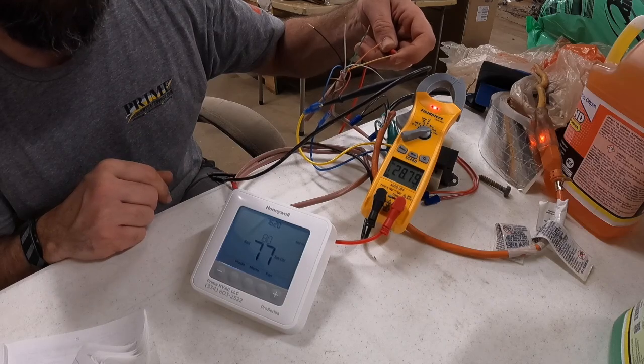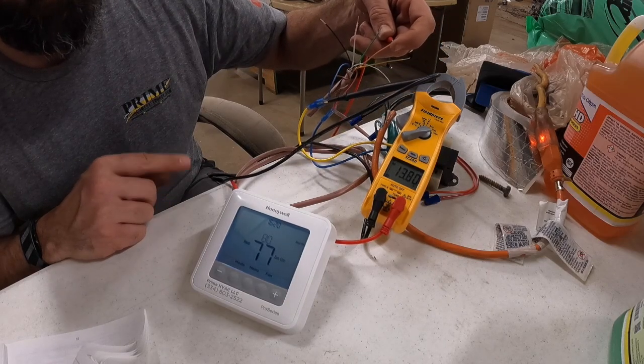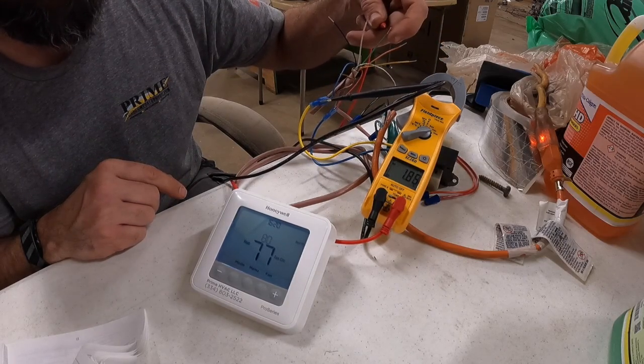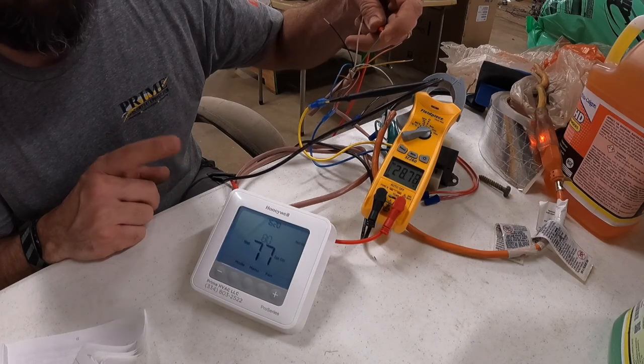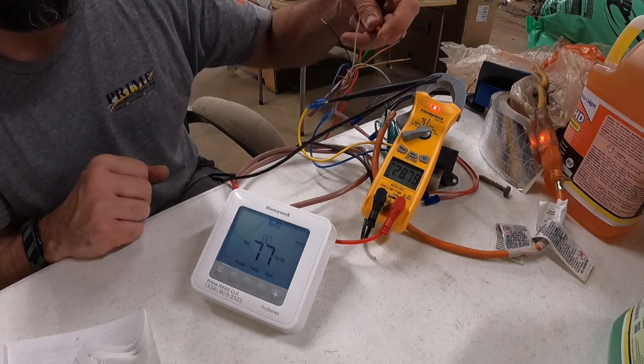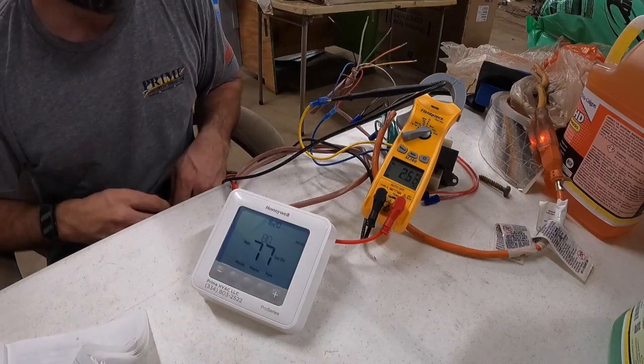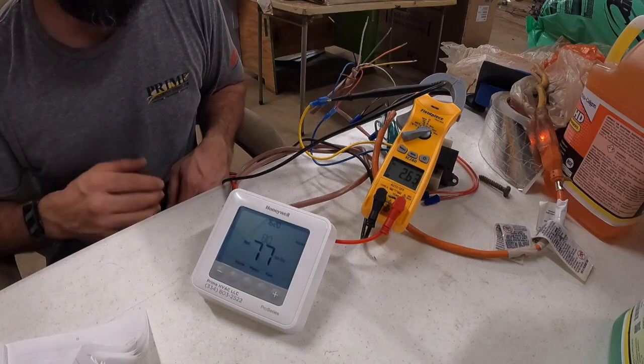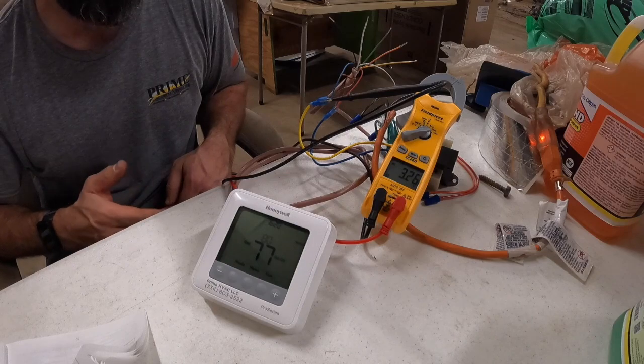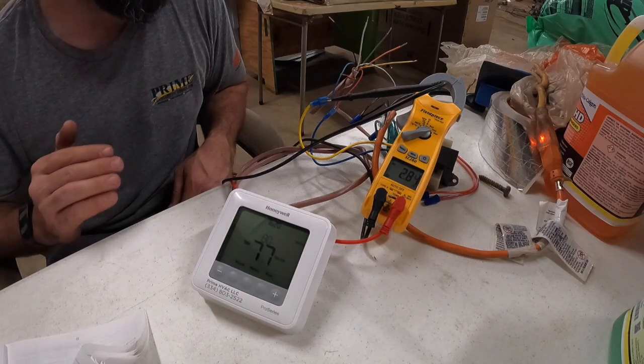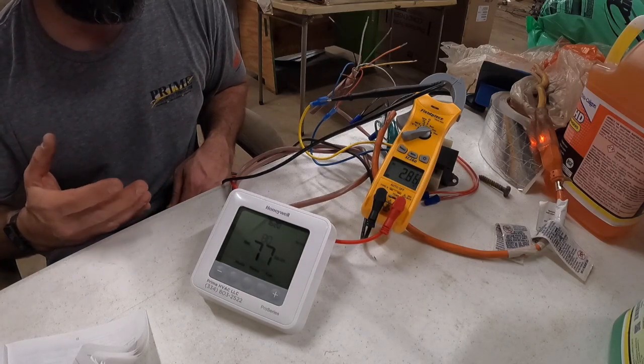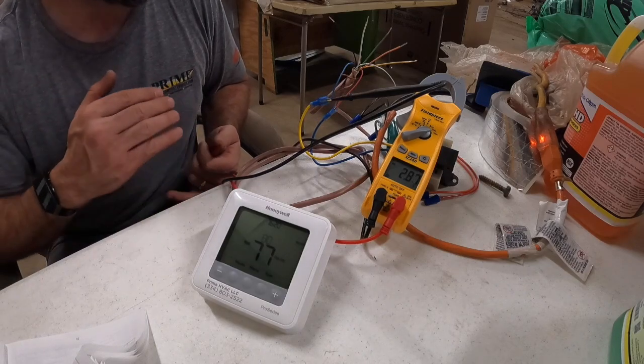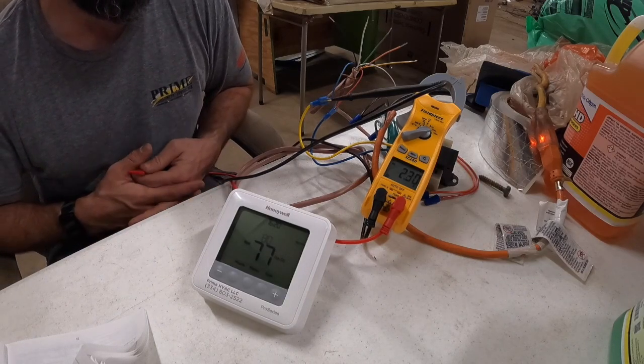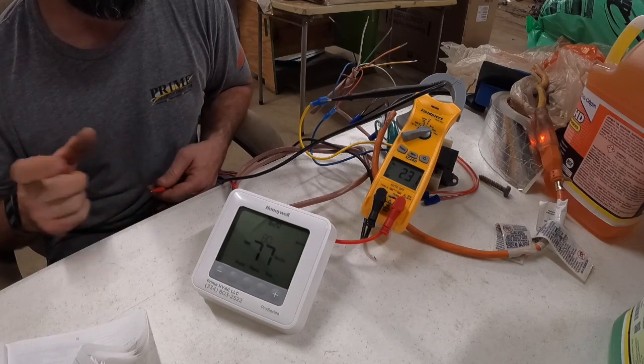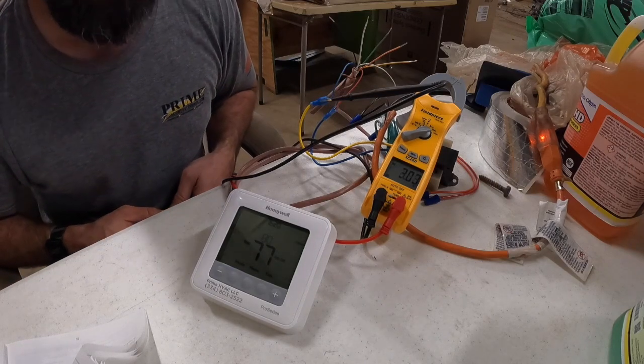So we're getting 24 volts on Y. We are not getting 24 volts on O because we're heating. And we've got 24 volts on G, which is the green wire. So your thermostat has called for heat. It's taken the power coming in from the transformer on the R terminal and designated it to Y and G to run the fan and to turn the outdoor unit on, the compressor and the condenser fan motor, and we're leaving the reversing valve in heat mode.